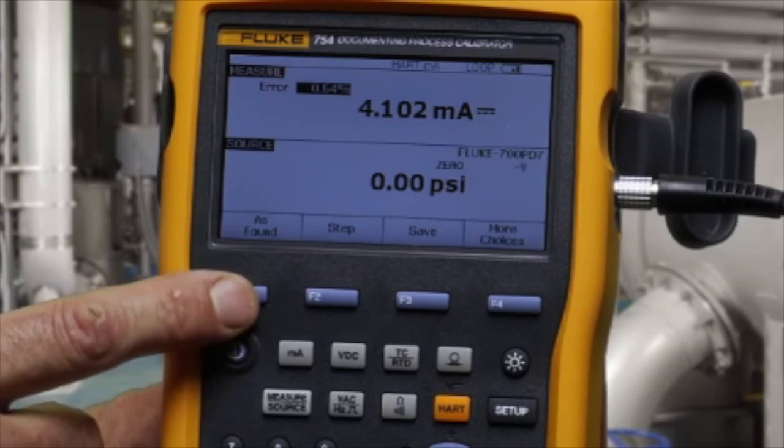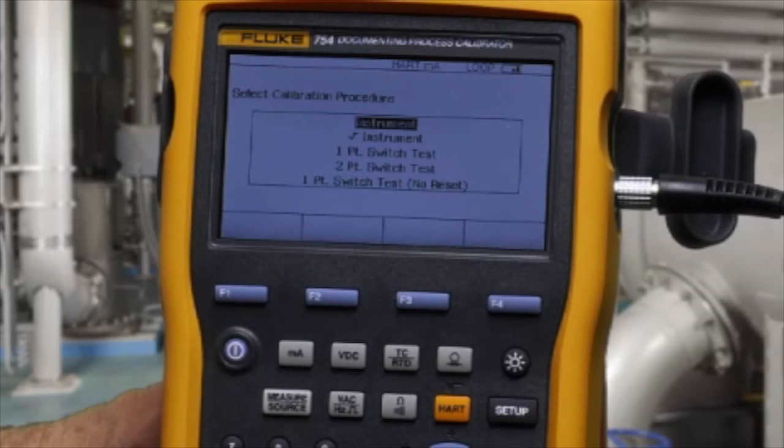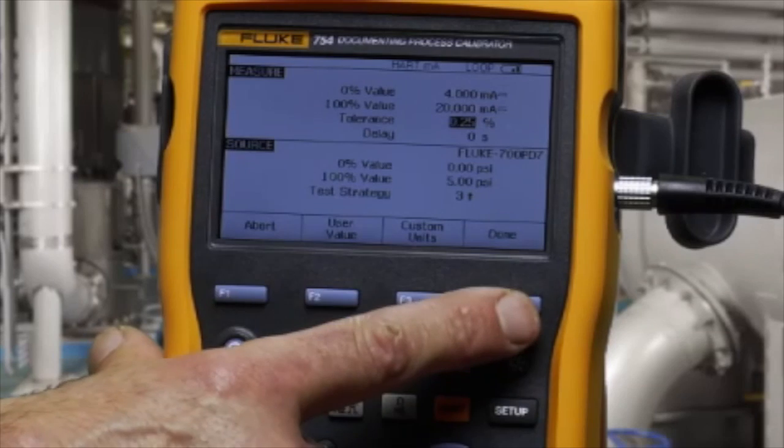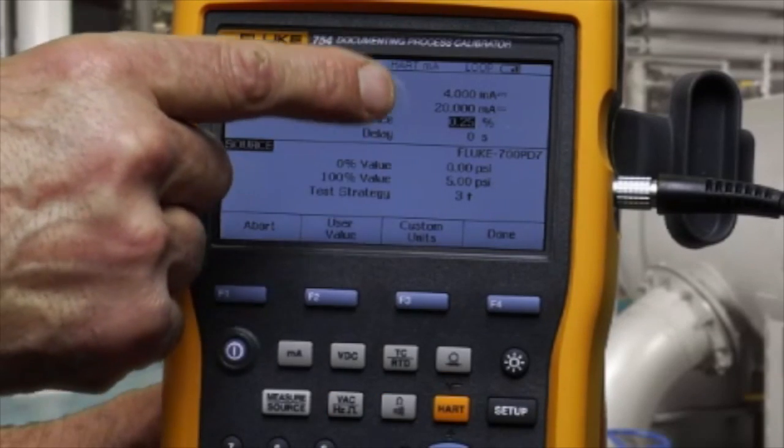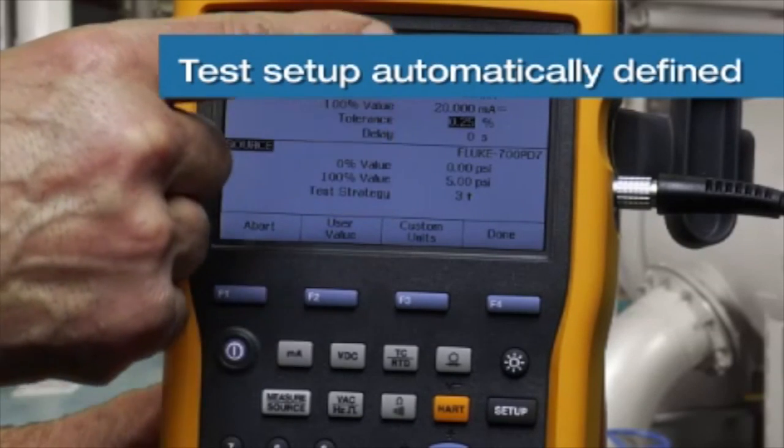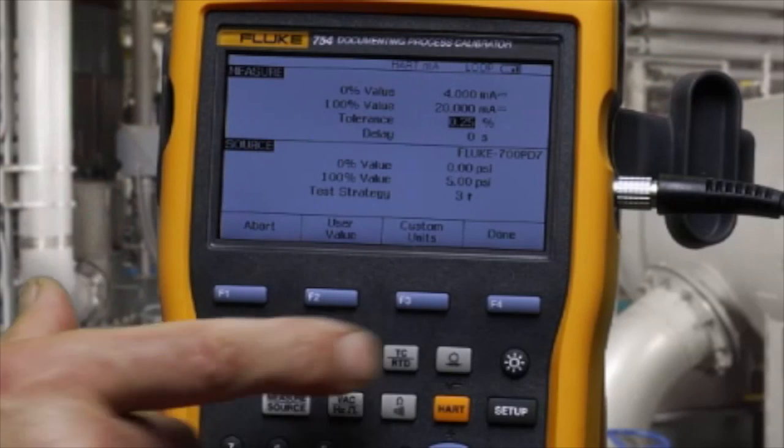To initiate the test as found for an instrument, everything is filled in. Confirm your test tolerance. You'll see the applied pressure values, zero and five PSI, for which we'll measure four to twenty milliamps to 0.25%.